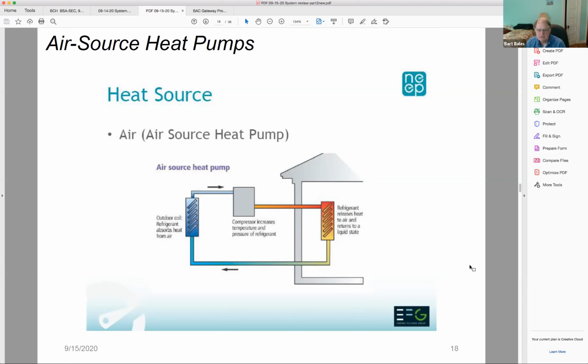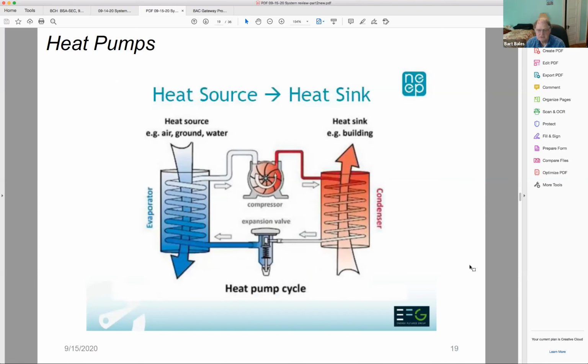Now we're used to calling things like this condensers in air conditioning. The outside coil is a condenser when we're doing air conditioning, but it is an evaporator when we're doing heating. All that happens is that the flow is reversed in these systems to accomplish both heating and cooling. You can see that a key element that was left out of the other drawing is this little expansion valve, which drops the pressure down and lets the magic of the heat pump cycle work.